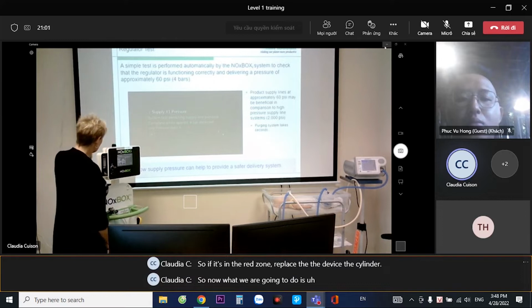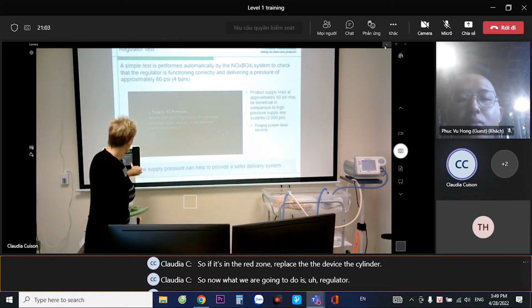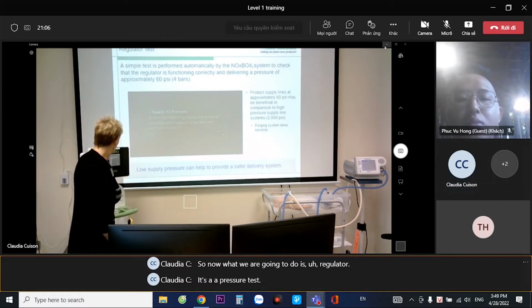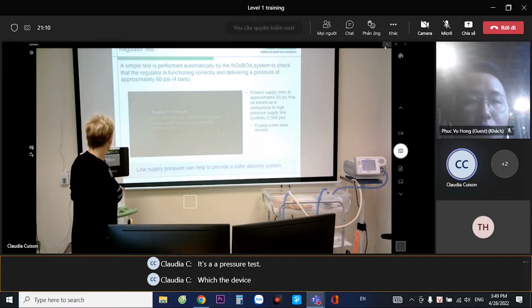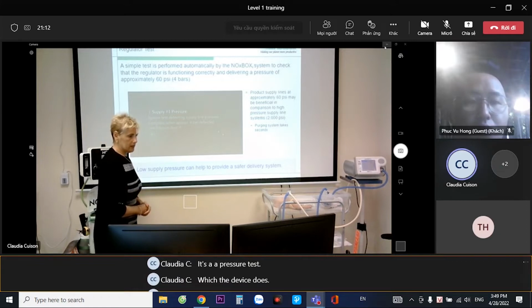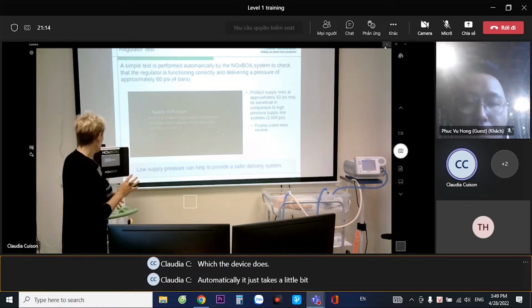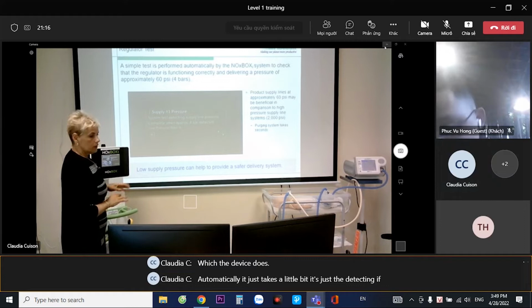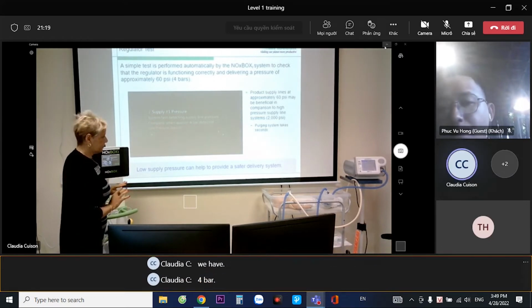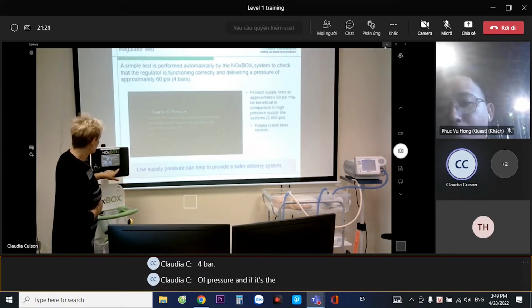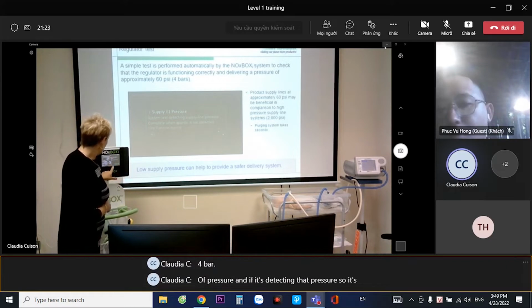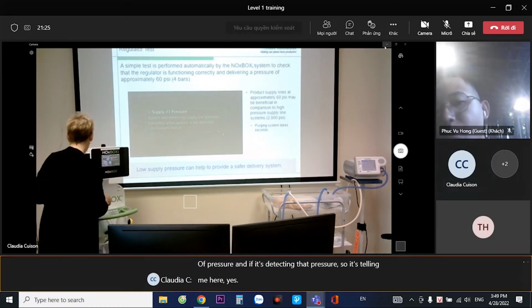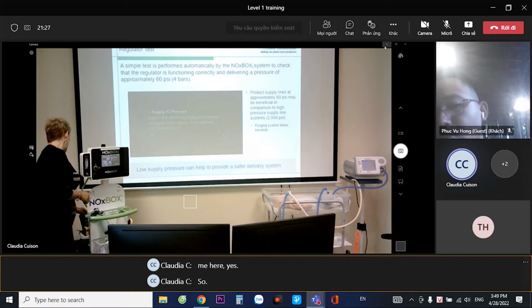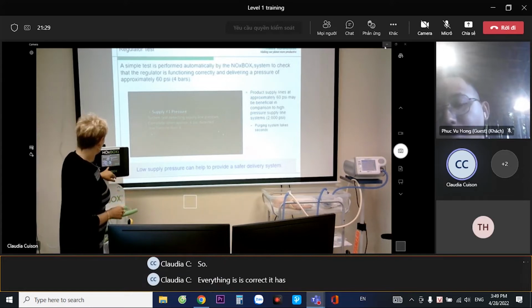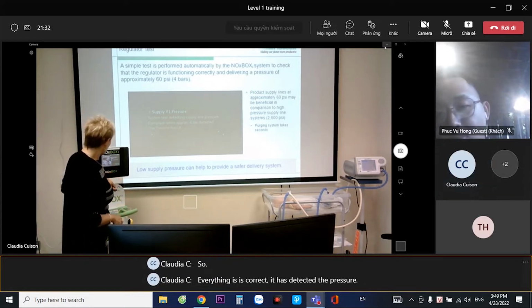So now what we are going to do is a regulator pressure test, which the device does automatically. It just takes a little bit. It's just detecting if we have 4 bar of pressure. So it's telling me here, yes. So everything is correct. It has detected the pressure.